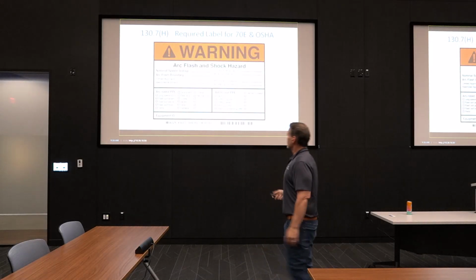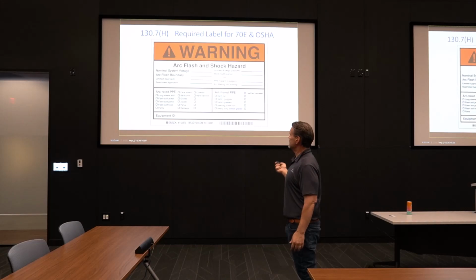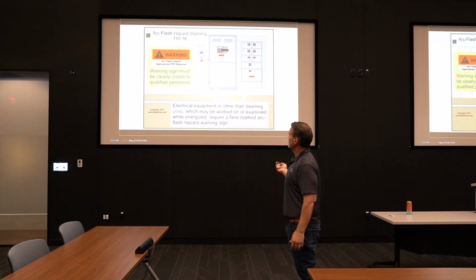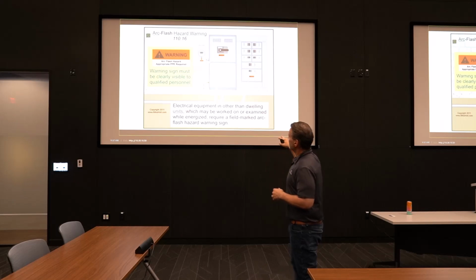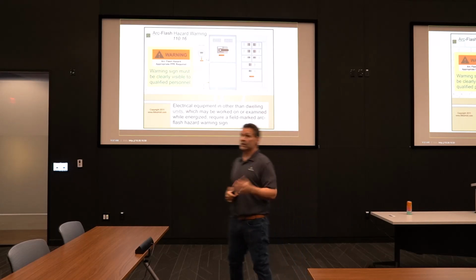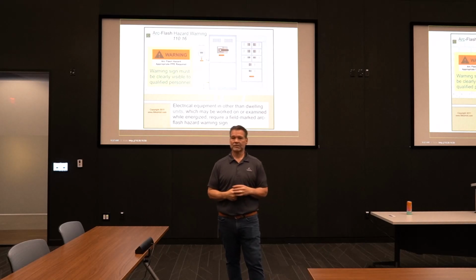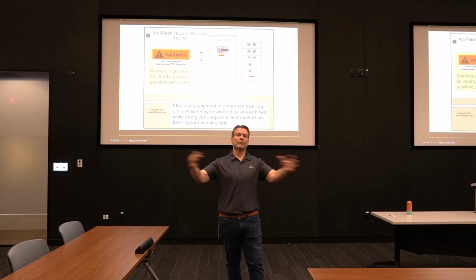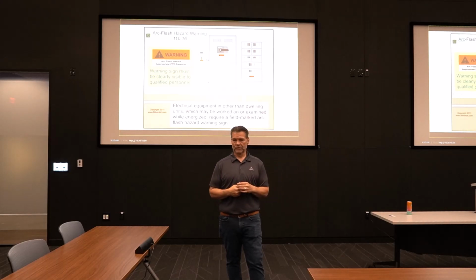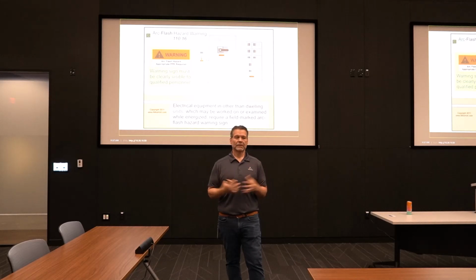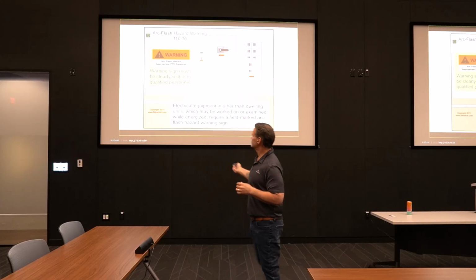Here's just a quick photo of an arc flash label. We're going to get into these more and talk about them a bit more. Arc flash labels are required on anything other than a dwelling unit that may have to be worked on while it's energized. I put this up there because all of our temporary services have to have arc flash labels on them, just so we're aware we're dealing with temporary power. We tend to treat temporary power differently than normal power, but it's not. National Electric Code says the only difference is it's temporary, not permanent. Everything else needs to be done to code, and it needs arc flash labels.